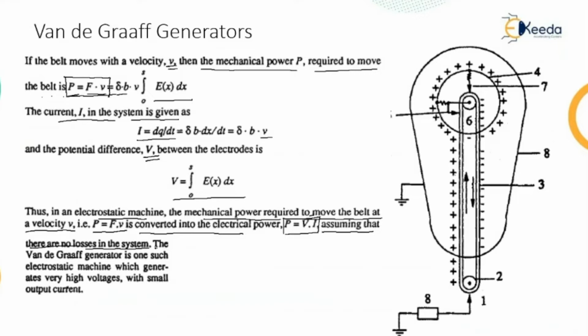So for that, we have a Van de Graaff generator, which is shown here. This Van de Graaff generator has different elements which are represented here. It is the electrostatic machine which generates very high voltage with small output current. For the testing purpose, the amount of current required is very small, but the amount of voltage which is required should be very, very high.